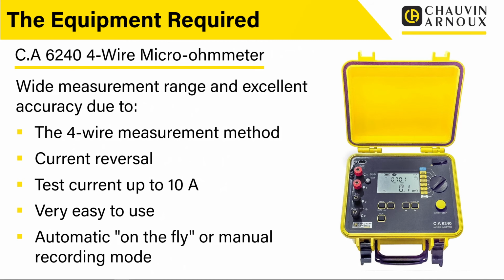You've got your current and potential terminals. It does the current reversal, so when we're talking about the thermocouple effects, we've got the current reversal that we can do in there as well, which is good. It's got a test current up to 10 amps. So generally a lot of the tests are carried out at lower than that, but to get up to the highest accuracy range, that would be a 10 amp test.